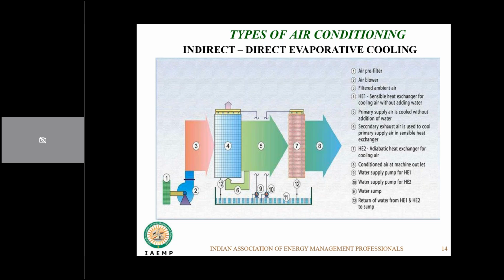I had the opportunity of using this on multiple occasions in some of my projects, where for a technical floor in a pharmaceutical area, we needed almost around 20,000 CFM air coming in. So for a facility, we used this 10,000 CFM indirect system. We didn't use the secondary part of it, the direct system. And normally I would have 40 degree air coming in. So we used this indirect system and got around 33 to 35 degree air coming in during peak summer. So I could reduce the load on the individual system, where they would have 40 degree air coming. Instead of that, we now have 35 degree air coming in. So we could reduce that load by 5 degrees centigrade.